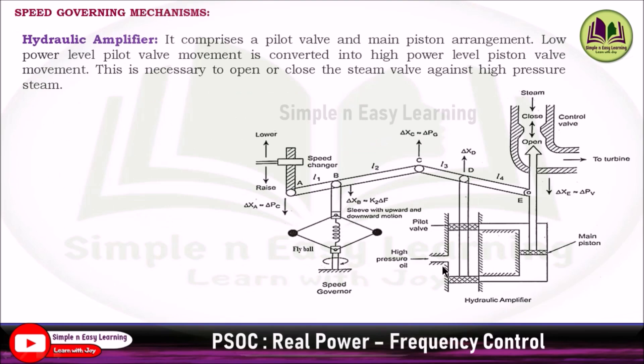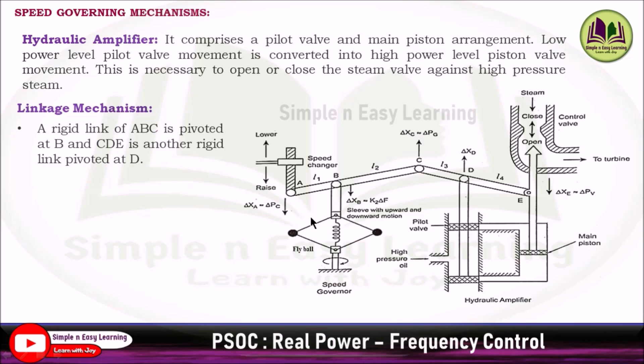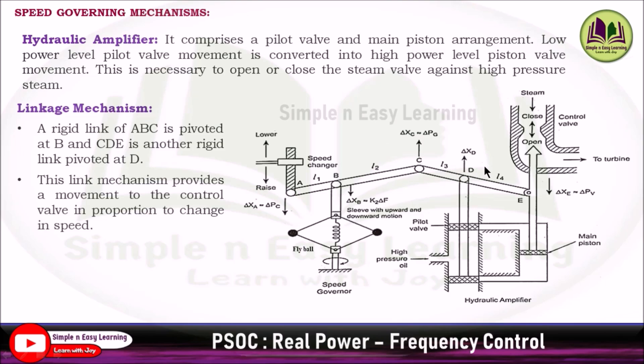The hydraulic amplifier comprises an upper pilot valve and a lower pilot valve. These two valves close the cylinder opening, and the main piston is inside the cylinder. High pressure oil enters through this inlet. These pilot valves are called low power level pilot valves. The low power level pilot valve movement is converted into high power level piston movement, so that it can open the steam valve and allow more steam to enter the turbine.